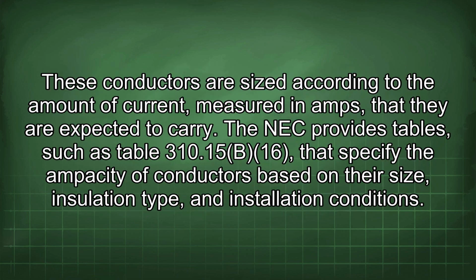These conductors are sized according to the amount of current, measured in amps, that they are expected to carry. The NEC provides tables, such as Table 310.15(B)(16), that specify the ampacity of conductors based on their size, insulation type, and installation conditions.